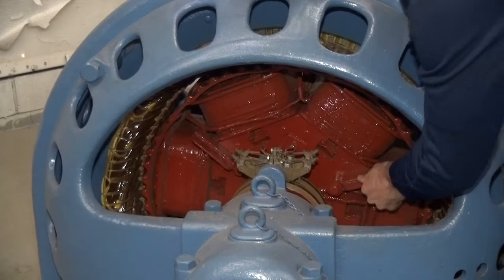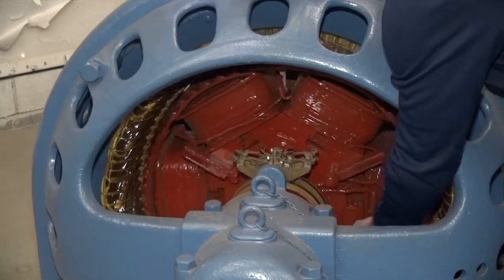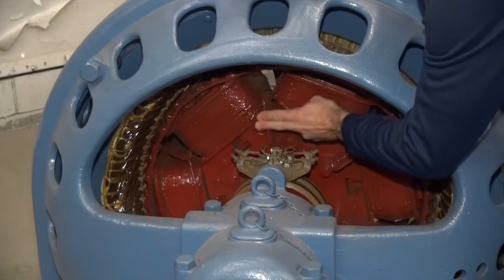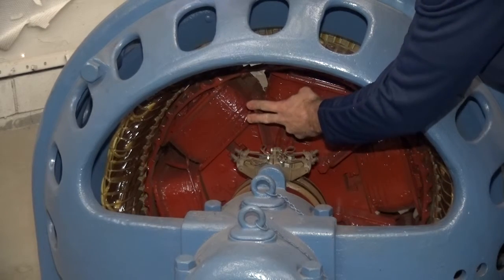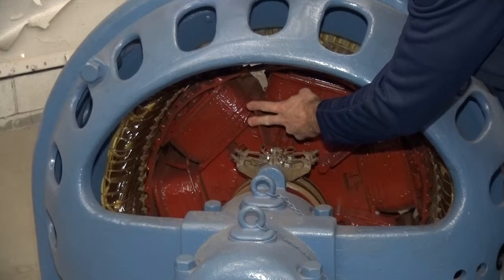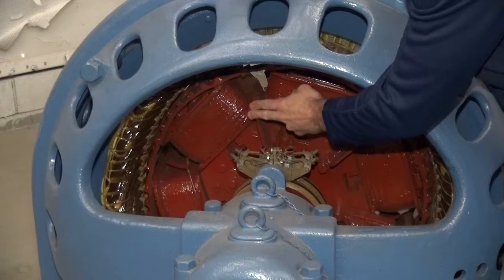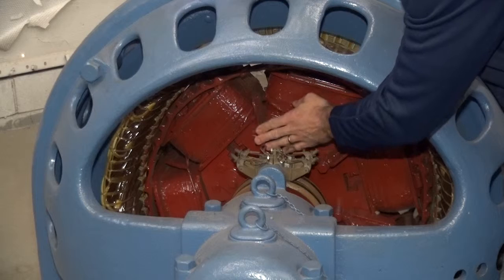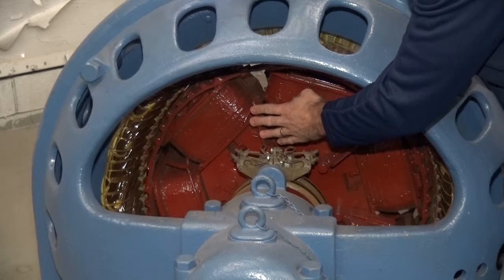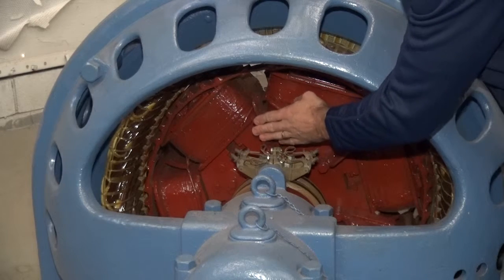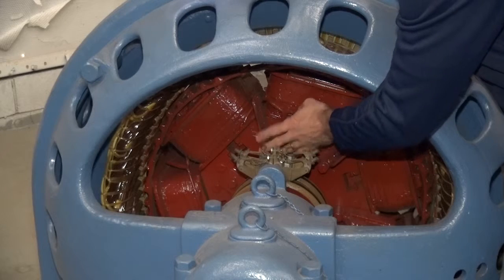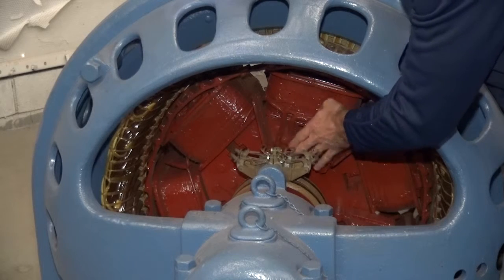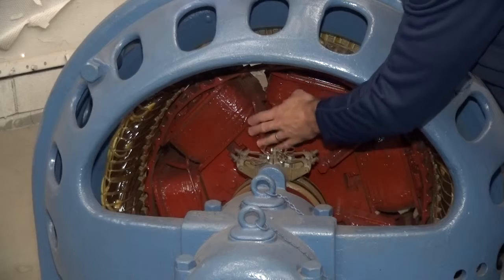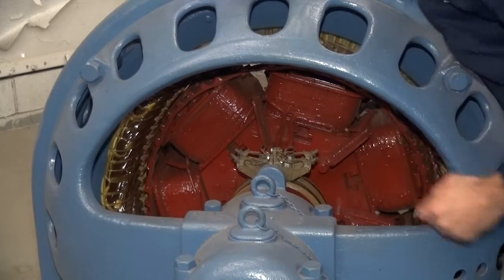This motor has very simple blower blades, which you can see here are simple flat pieces of metal. Some motors that operate at higher speeds will have very complex radial blowers, and slower speed units will typically have a blower similar to this with a bent piece of sheet metal. We should inspect these blowers carefully to ensure there's no corrosion or problems with the fasteners or evidence of contact.